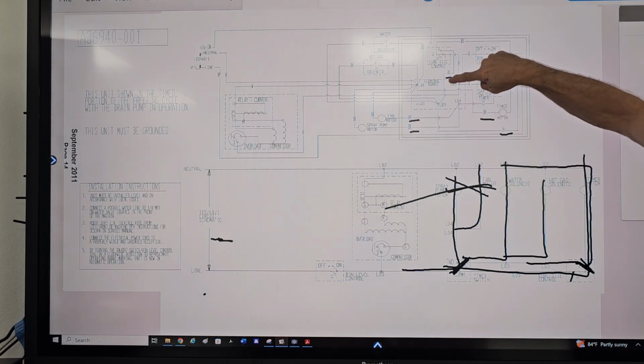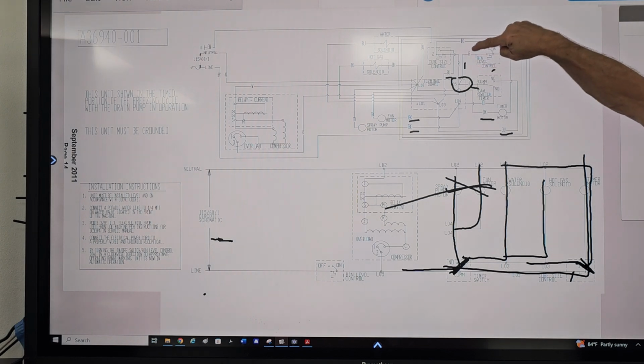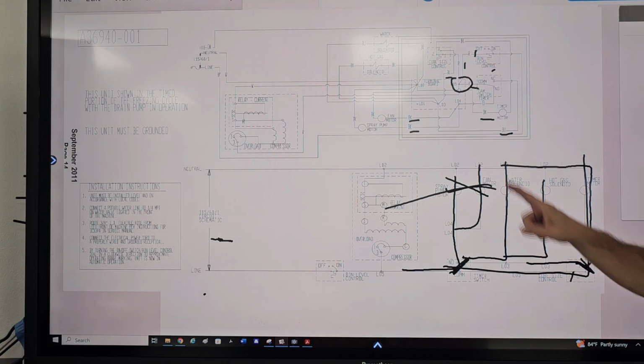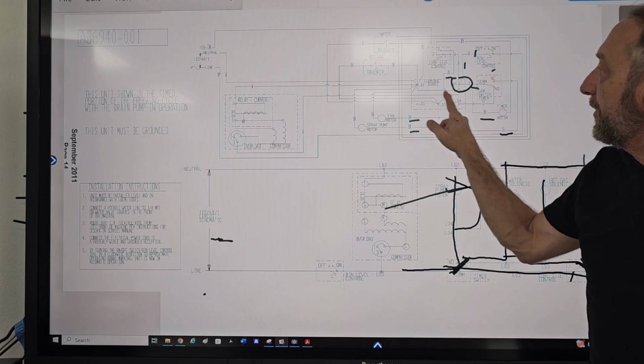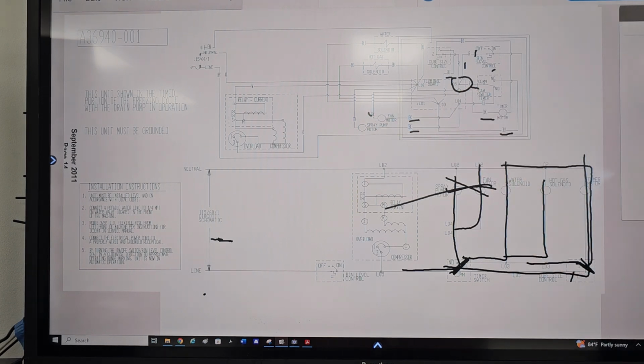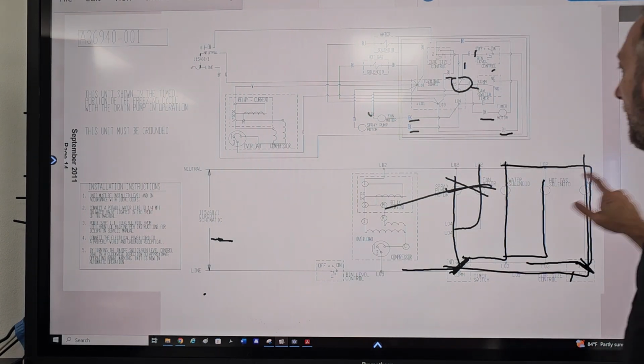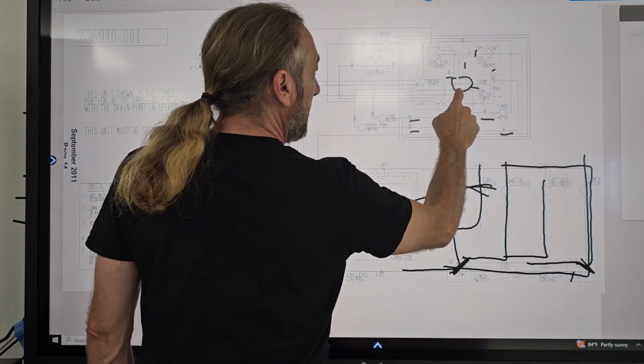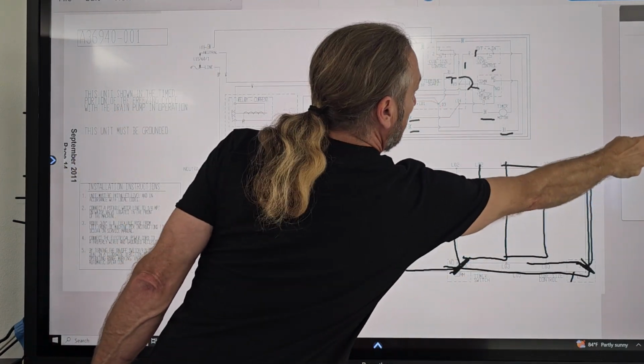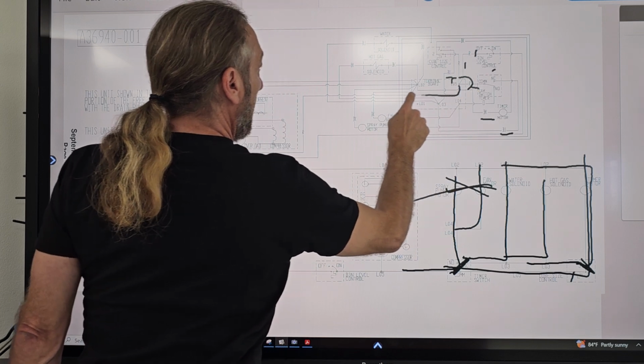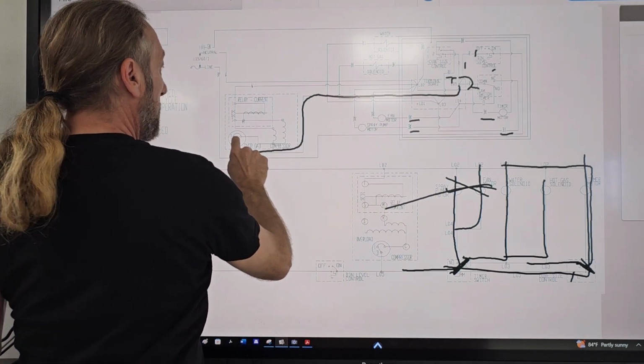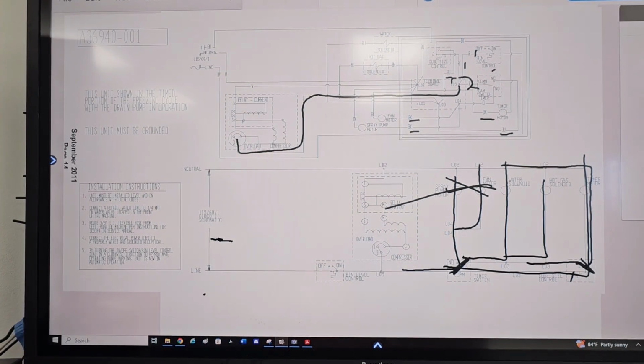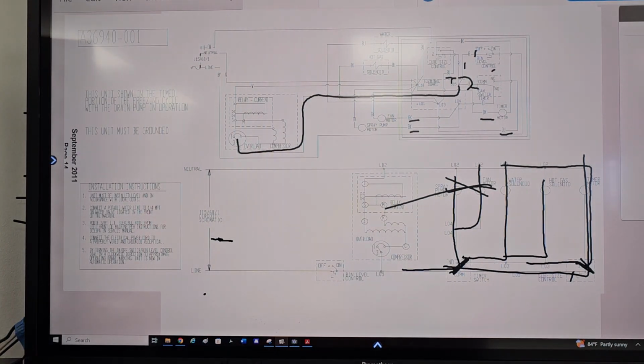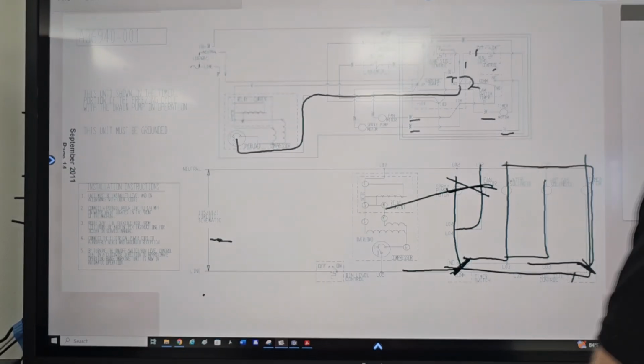I can see on L05 I have 1, 2, 3 red wires going to that terminal, and there's one other wire here, black, that are, no, that's not the black one, I'm sorry, I followed it wrong. It's this one right here, this wire right here, which is red going to the compressor. So that's just a terminal board where they connect multiple wires instead of using like a wire nut to connect them all together. Let's take a look at this.